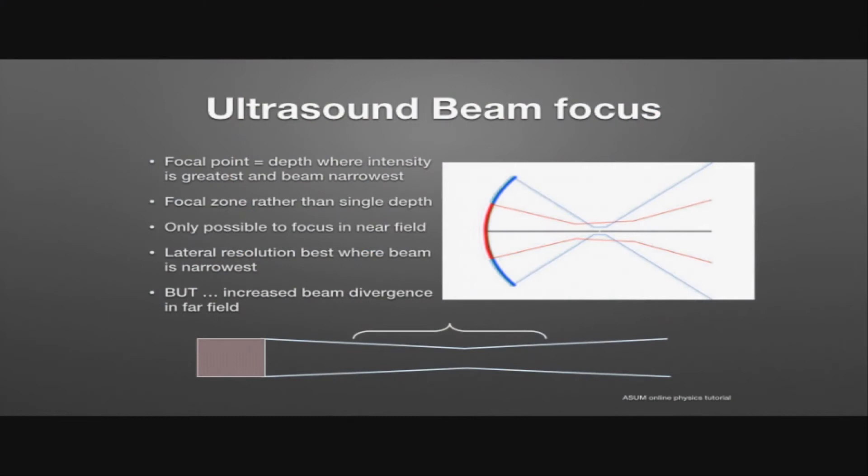So now let's consider trying to focus this ultrasound beam a bit more. And this is going to happen in what's known as the focal point, or the focal zone. And this is the depth where both the intensity is greatest and the beam is the narrowest, and this will give us some of the best resolution possible. It's actually, rather than a single depth, it's more of a focal zone. And again, it is only possible to get this focal zone in the near field.